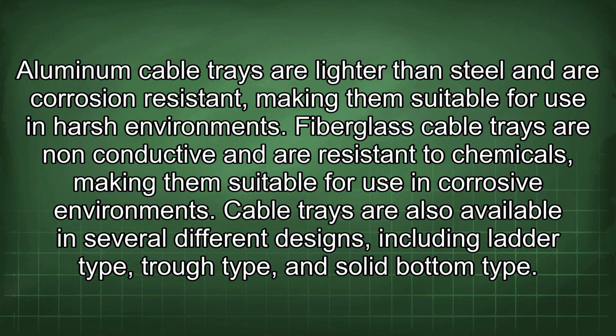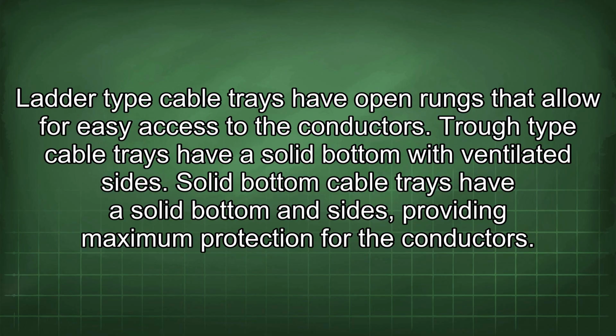Cable trays are also available in several different designs, including ladder type, trough type, and solid bottom type. Ladder type cable trays have open rungs that allow for easy access to the conductors. Trough type cable trays have a solid bottom with ventilated sides. Solid bottom cable trays have a solid bottom and sides, providing maximum protection for the conductors.